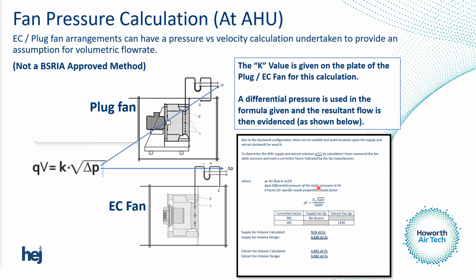So at the bottom here, I've just given you an example of one of the tests that we've carried out on one of the validations, because we couldn't get an adequate test position. And this is what we've done. We've done this exact test that we've got on this slide. The only difference is we've divided it by 3,600 to get the volume back into meters cubed per second, so we can report our values in the same unit within the report. One thing I would note is I know that this has been going on around the country in various projects, and BSRIA don't see this as an approved method of assessing the volume down the air handling unit, but I think it's important that everybody's aware of it.